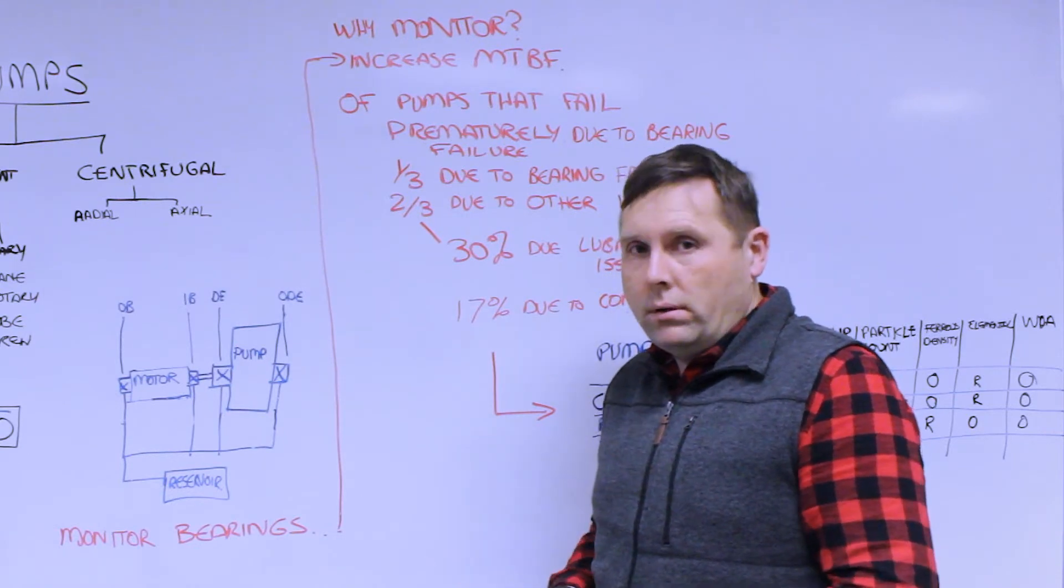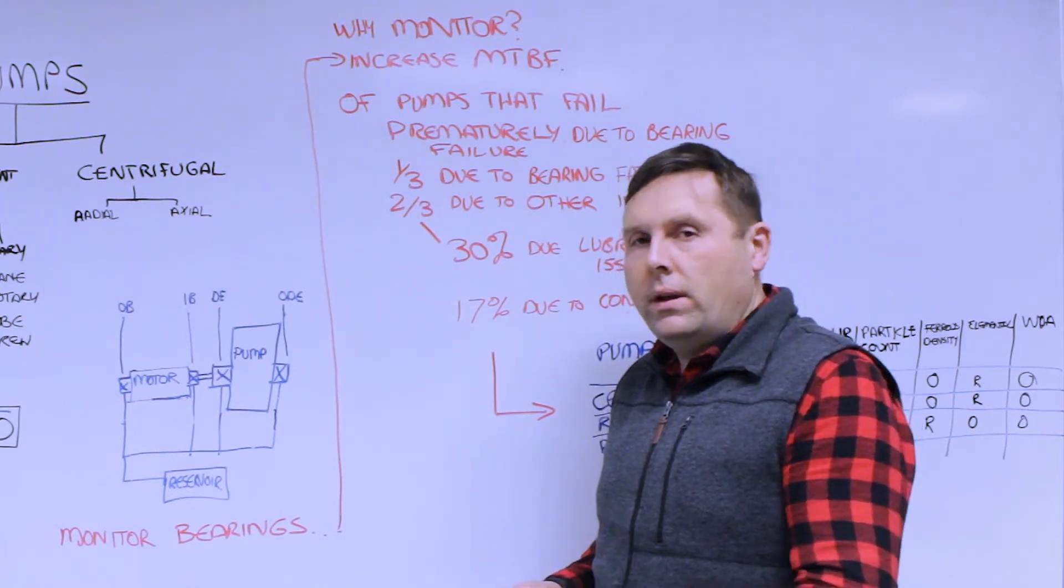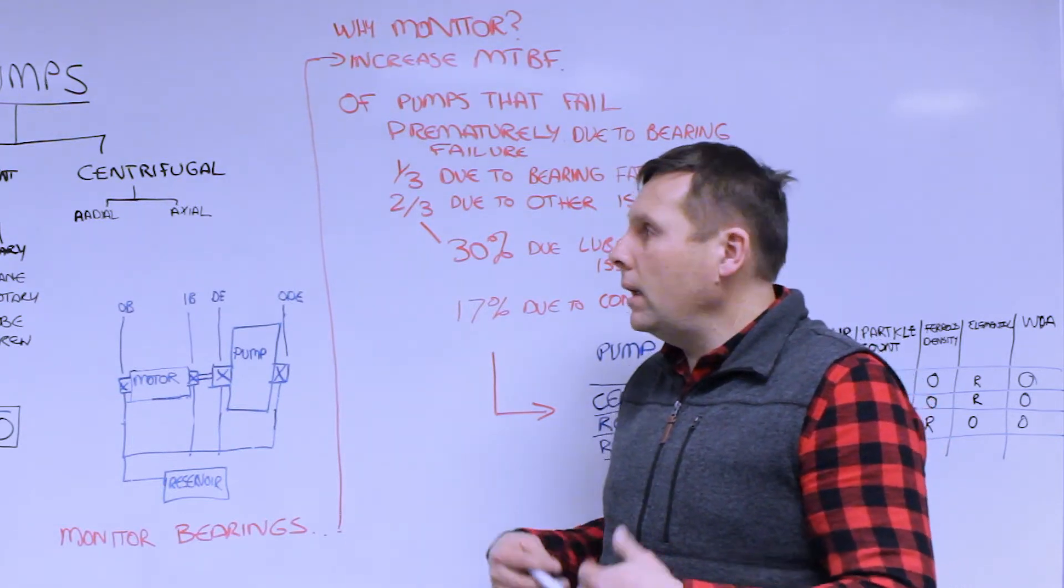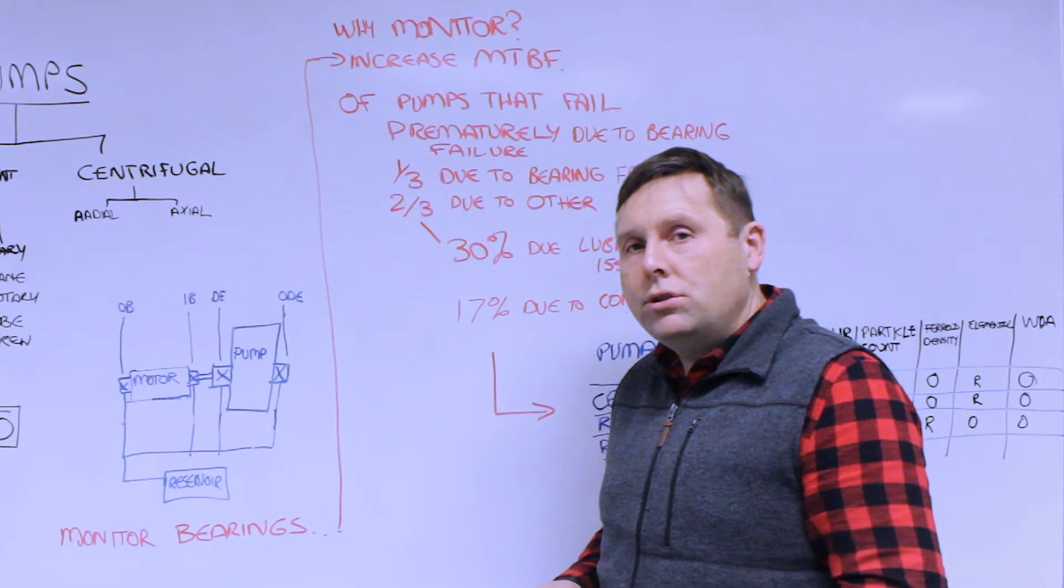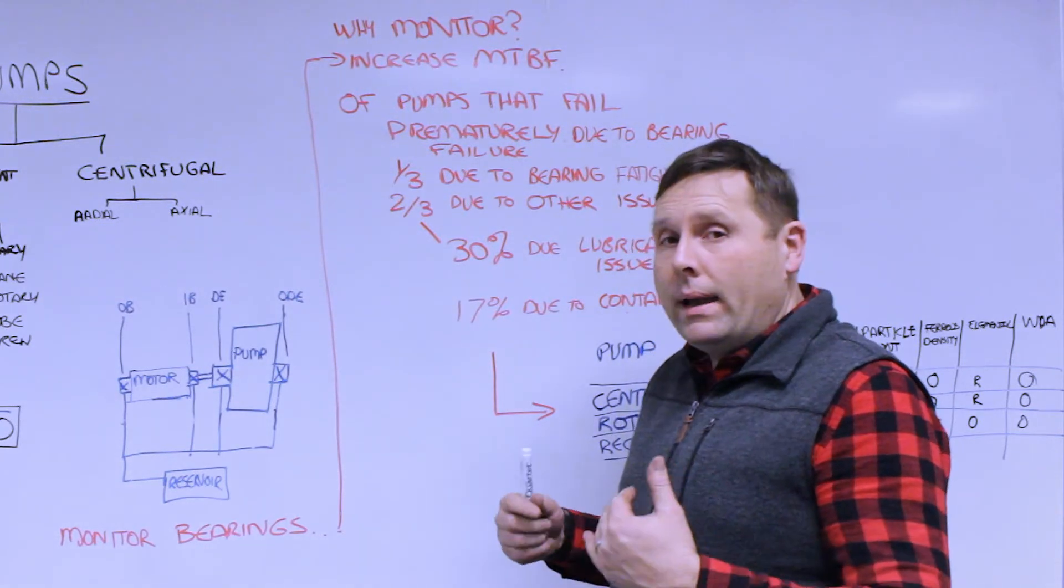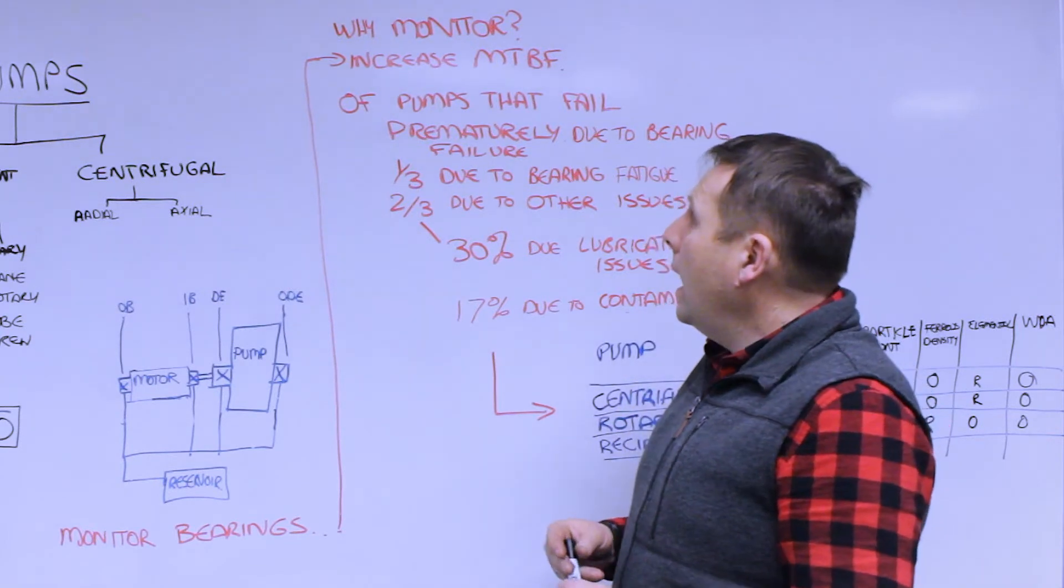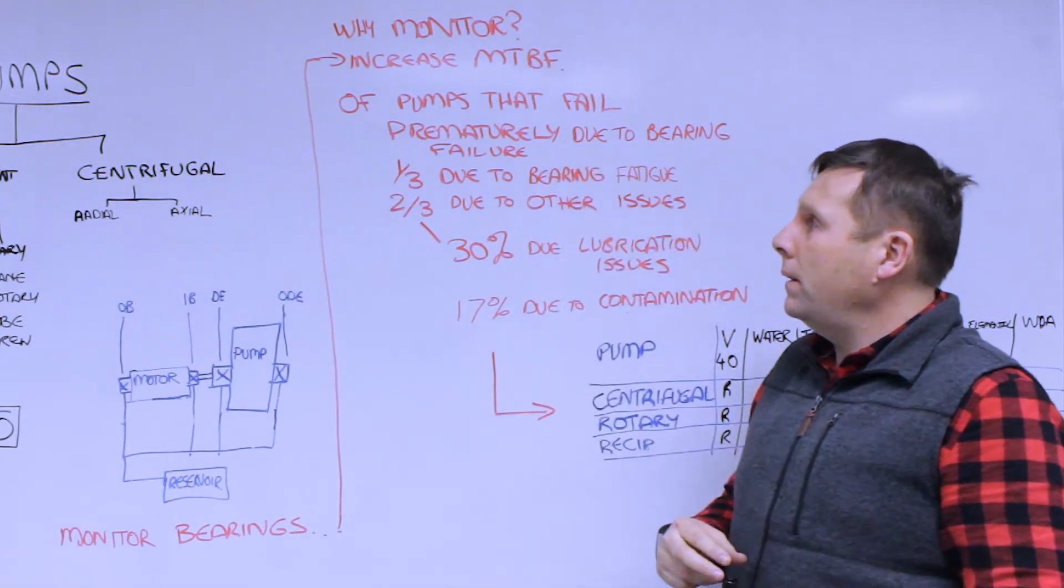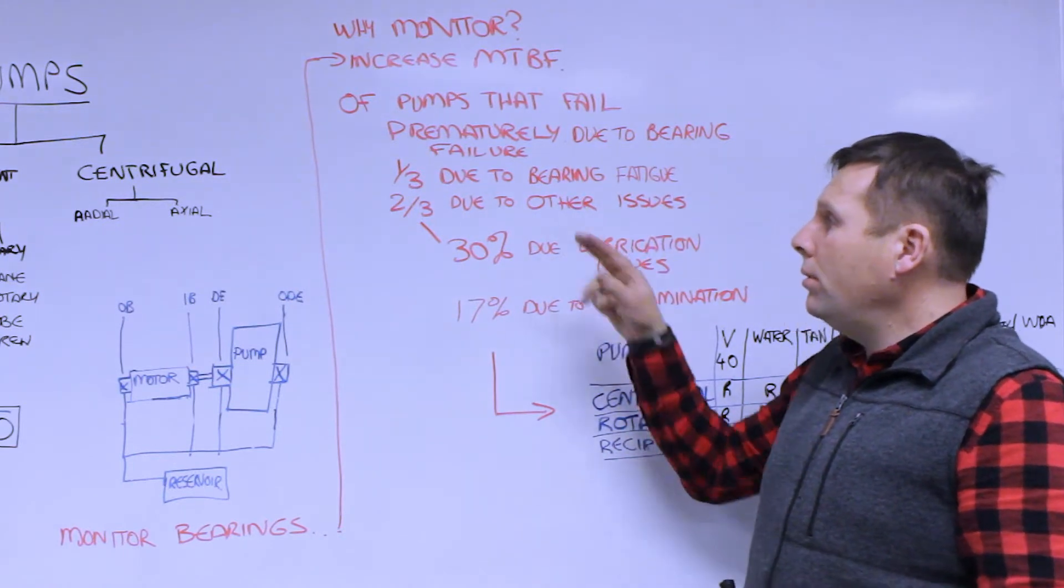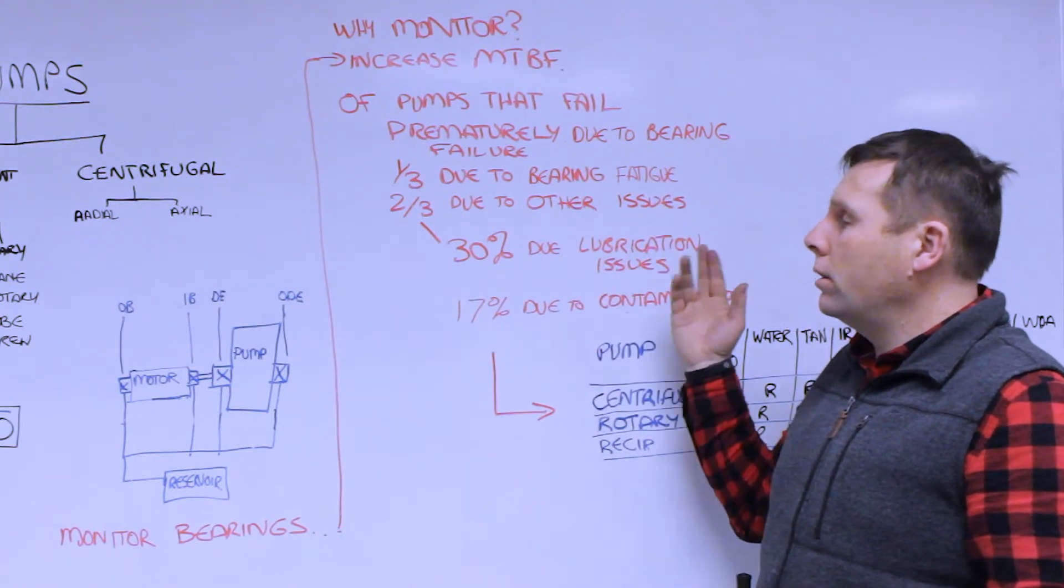Pumps can fail through a variety of reasons - through vibration, due to the impeller breaking down, or due to alignment issues. However, the majority of pumps that fail by bearing-related issues - of those that fail prematurely due to bearing failure, one third is due to bearing fatigue and two thirds of those failures is due to other issues.